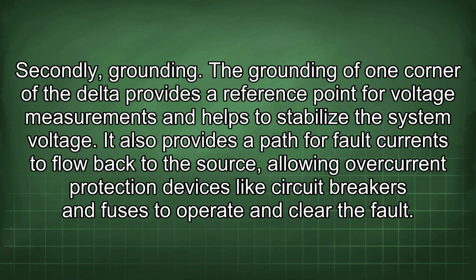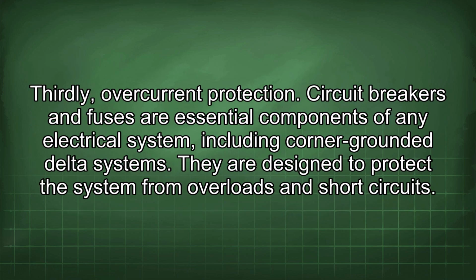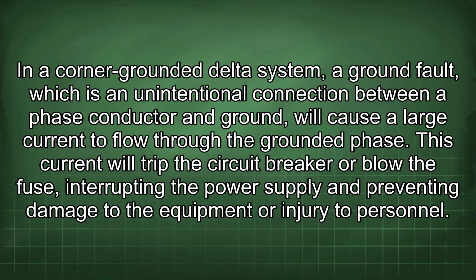Secondly, grounding. The grounding of one corner of the delta provides a reference point for voltage measurements and helps to stabilize the system voltage. It also provides a path for fault currents to flow back to the source, allowing overcurrent protection devices like circuit breakers and fuses to operate and clear the fault. Thirdly, overcurrent protection. Circuit breakers and fuses are essential components of any electrical system, including corner-grounded delta systems. They are designed to protect the system from overloads and short circuits. In a corner-grounded delta system, a ground fault, which is an unintentional connection between a phase conductor and ground, will cause a large current to flow through the grounded phase. This current will trip the circuit breaker or blow the fuse, interrupting the power supply and preventing damage to the equipment or injury to personnel.